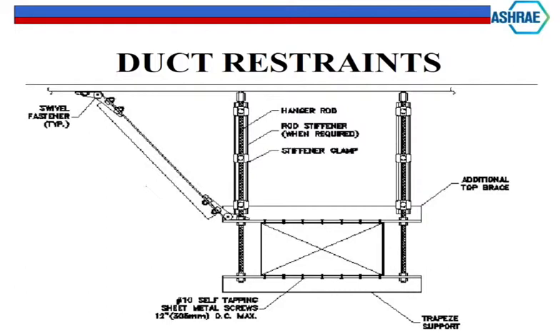You go to pull it apart, it'll just rip the steel out, right? So you end up having to put steel on top and bottom to try and keep this in place as a rectangle as it's starting. That way your surfaces might still be able to be working. So you've got steel above and below, and we've got sheet metal screws holding it in. So this stays as one rigid rectangle now. And then you have your braces off of the steel work, right? Someplace obviously that can hold on to the steel, hold on to the braces and transfer forces.